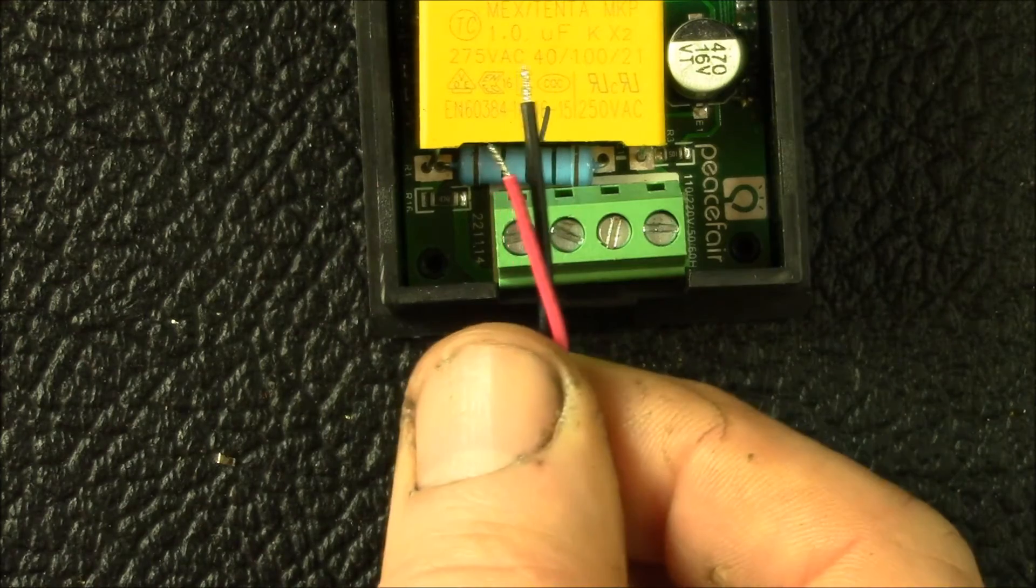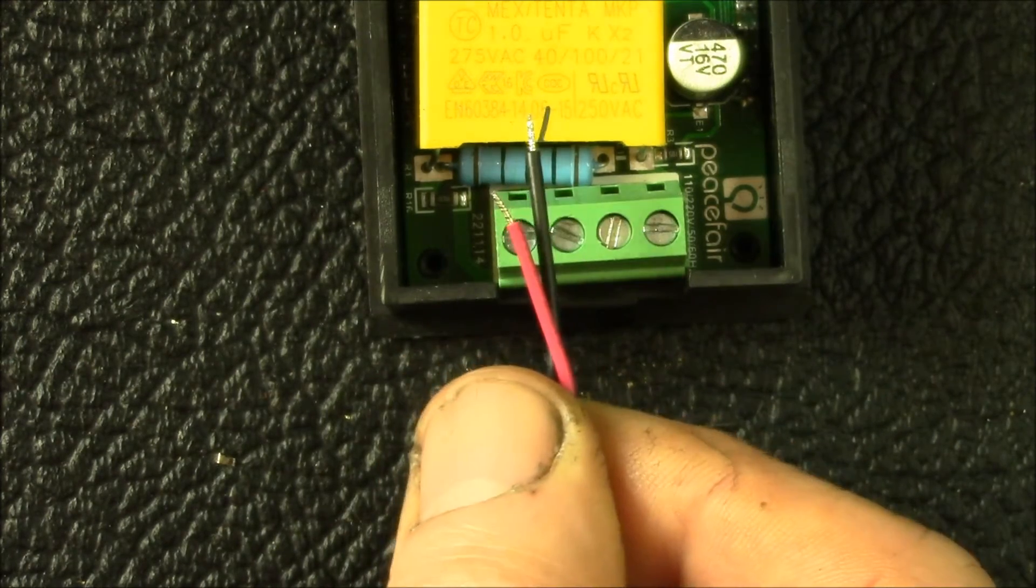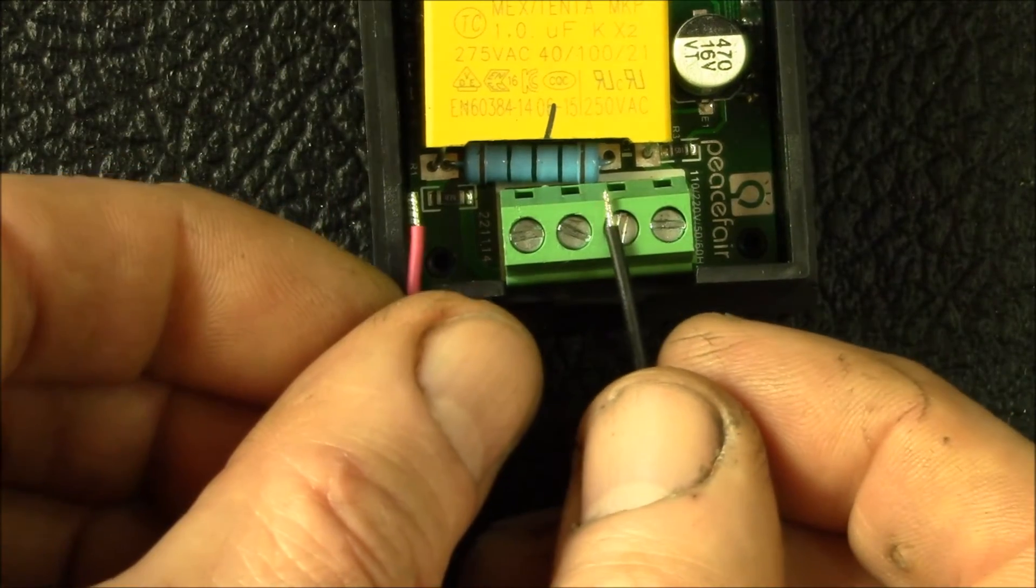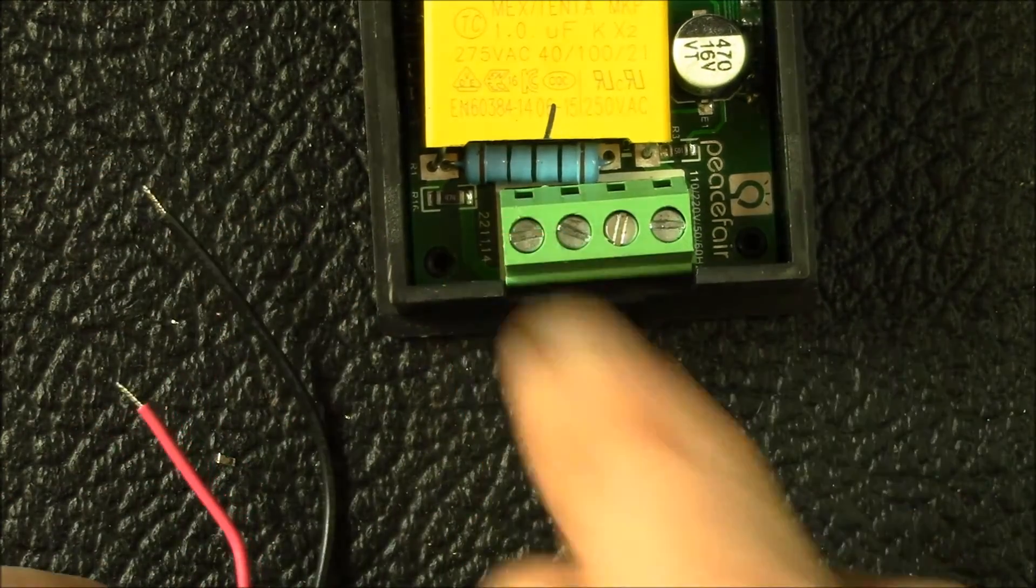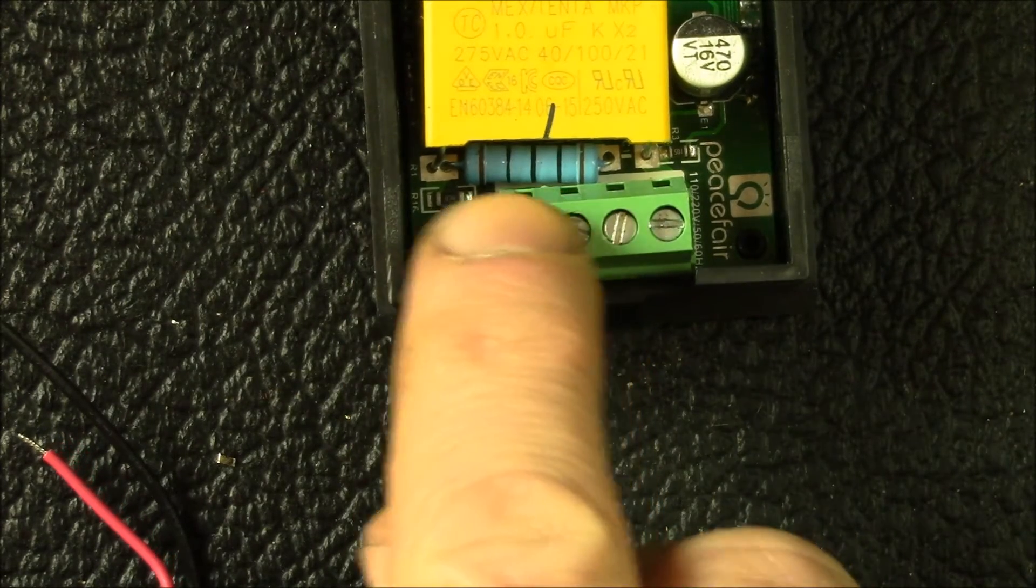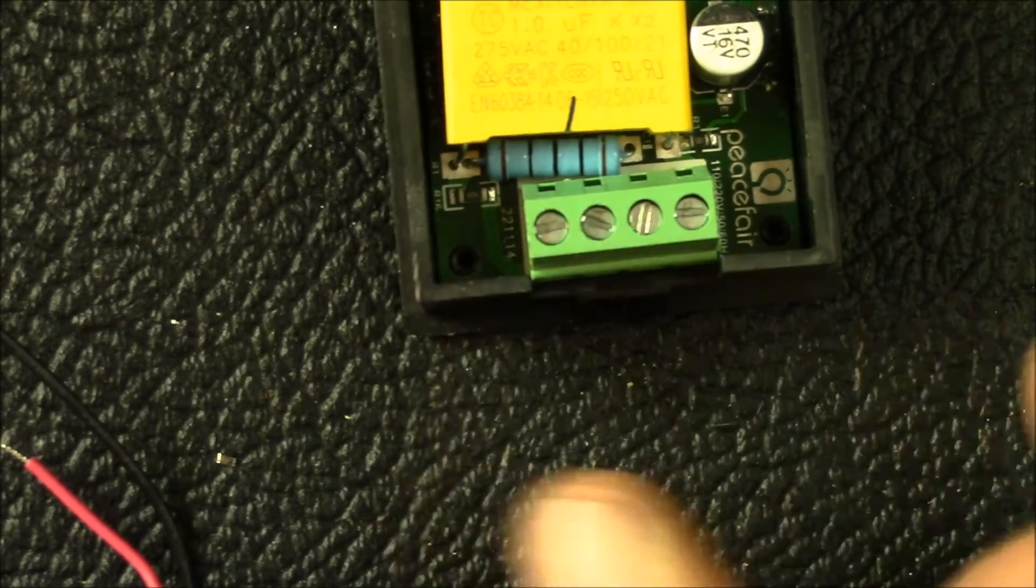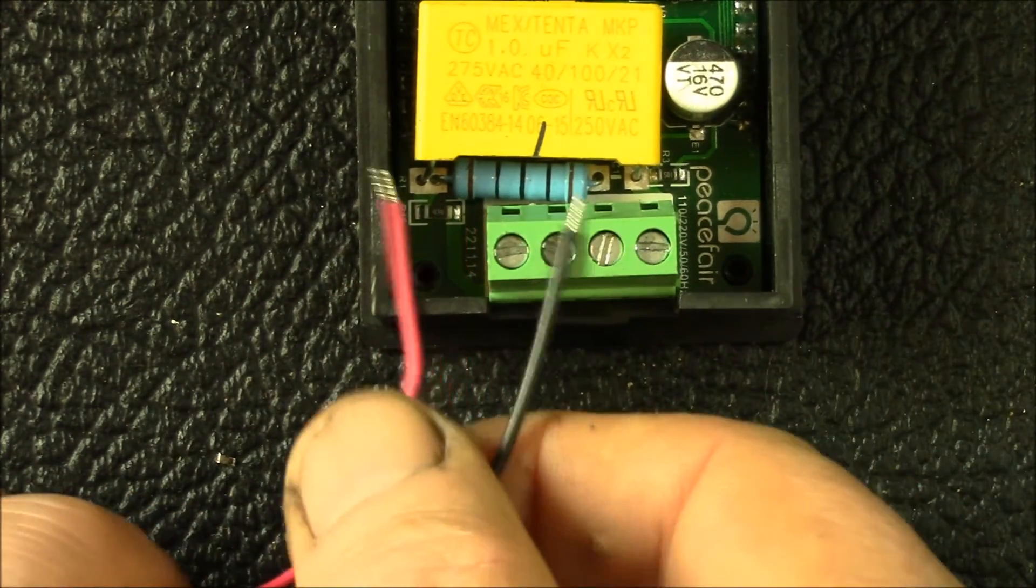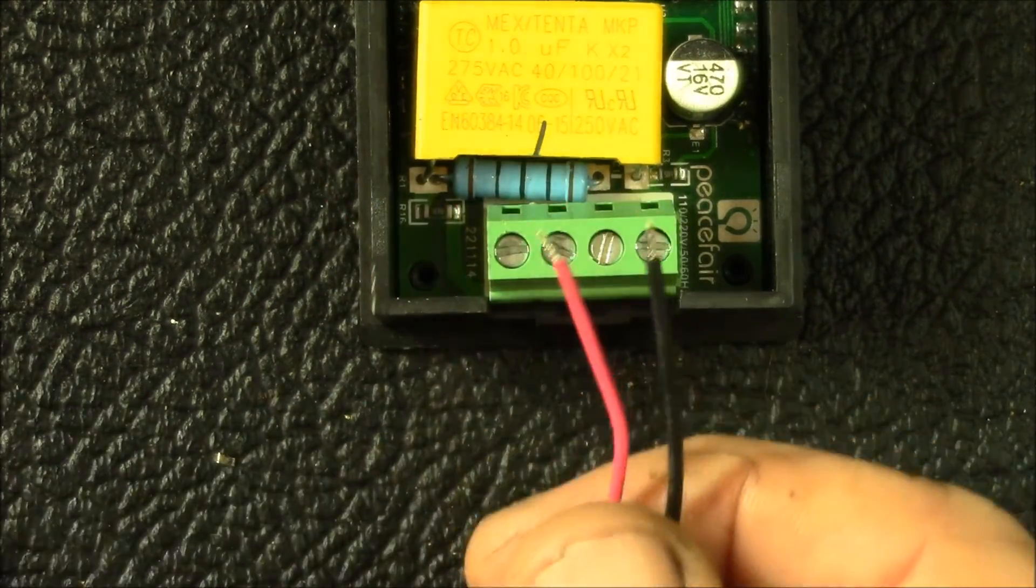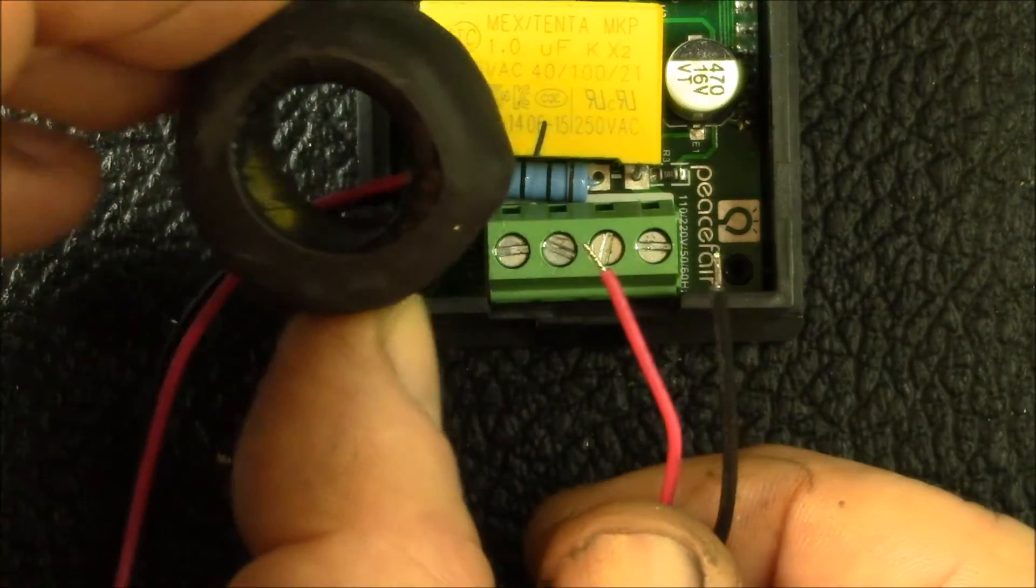Since this was 1000 to 1, if you have 100 amps flowing through this CT you're going to have 100 milliamps flowing through these two wires. If you put those across that resistor, 100 ohms with 100 milliamps is 10 volts, so you're going to get 10 volts full scale across that resistor.